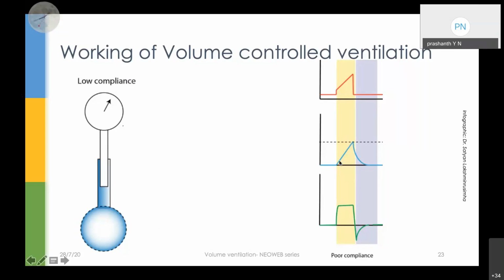All right, so see this, then your pressure will become a dependent variable here. As your flow is constant, the volume starts increasing and reaches this point. You see the flow curve has become flattened here, but not your pressure wave. The pressure wave is constantly increasing. It is peaking before the end of inspiration, and then once your volume has stopped, the pressure goes down.